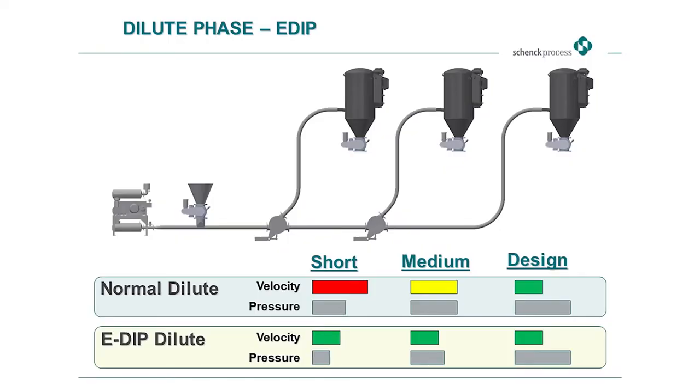However, this also means that in nearly every case, there's more air and hence velocity than is required to operate the system. Now, it may be 5% more, or it may be 25% more. It's rarely ever quantified. As the price of VFDs came down dramatically over the last 10 years or so, we began to see more blowers capable of speed control. But you had to have a reason to adjust the speed, and if the system was working, you were unlikely to slow it down much.